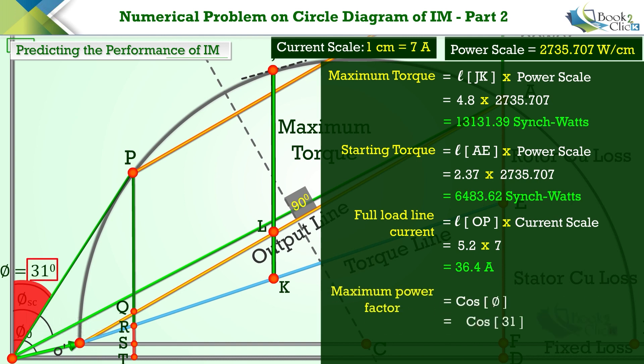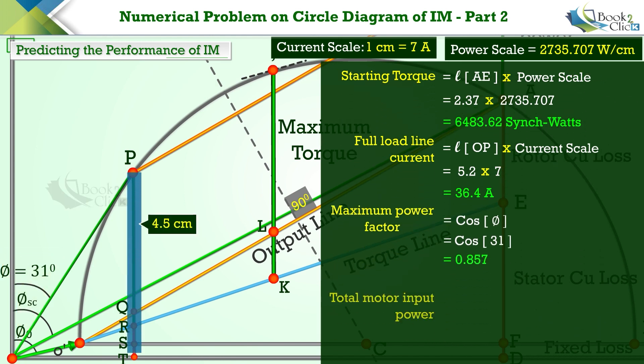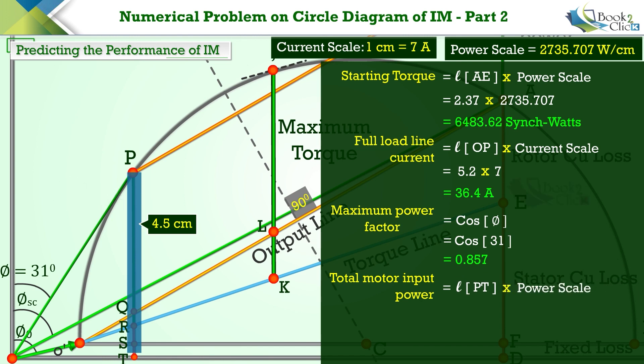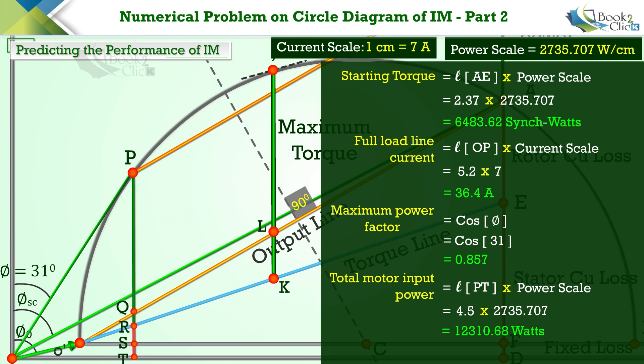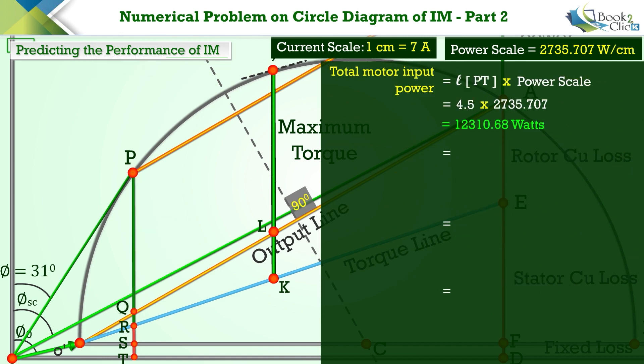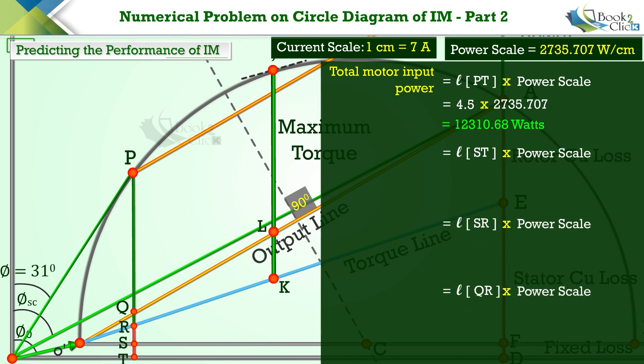The cosine of the full load lag angle gives the power factor of the motor. Cos of 31 degrees is 0.857. Multiply the length of line PT by the power scale to get the total motor input power. The length of line PT is 4.5 centimeters, giving a total motor input power of 12,310.68 watts.